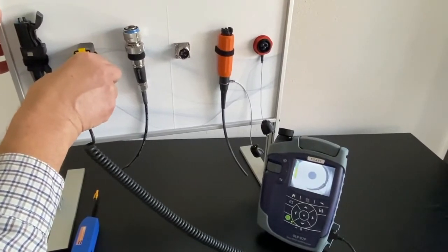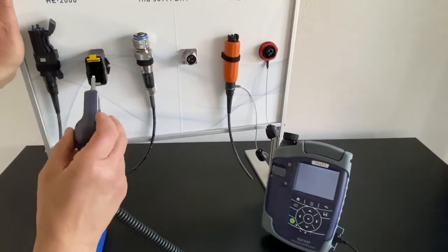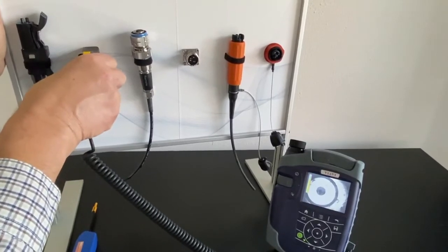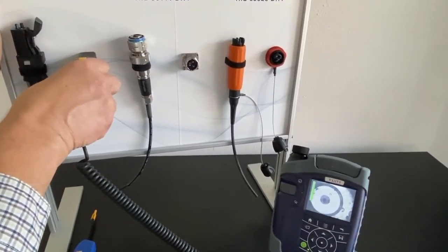Let me just find the focus — there you are. Now I will go to the other side and inspect. I have a zero-degree PC. This one is completely contaminated and it needs cleaning.